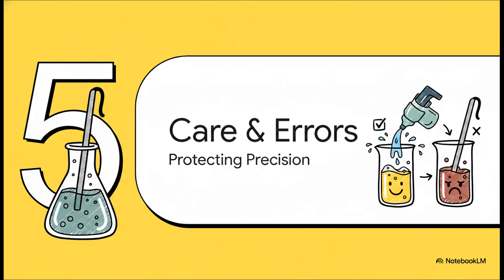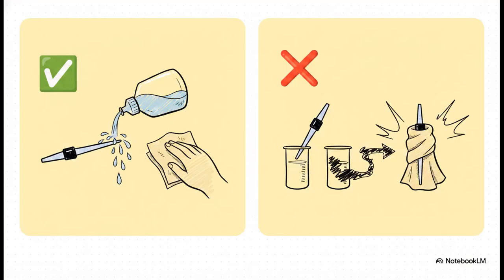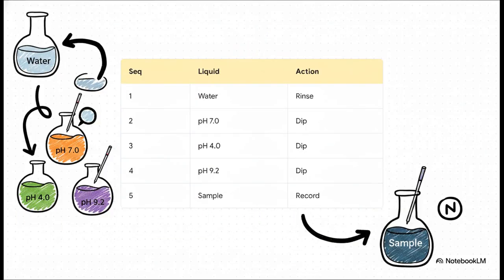Section 5. Proper care and common errors. Protecting your precision. Okay, so to protect your precision long-term, there are absolute do's and don'ts in the lab. You must rinse between buffers, and you always calibrate before a new measurement session. Conversely, if you skip rinsing between buffers, which by the way causes massive cross-contamination, or if you aggressively rub the electrode dry instead of gently blotting it, you are going to ruin your expensive equipment and your precision will absolutely plummet.